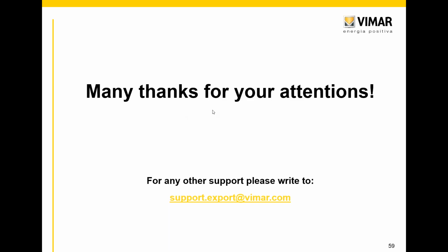Okay, another good question. Old BTicino system, yes. For the ones among you that already know the old generation, the components 99% are compatible after 2013. So if the installation is done in terms of push buttons, actuators, and so on, they are fully compatible. The old touchscreens, no. You can leave the old touchscreens there, but without the new functionalities.